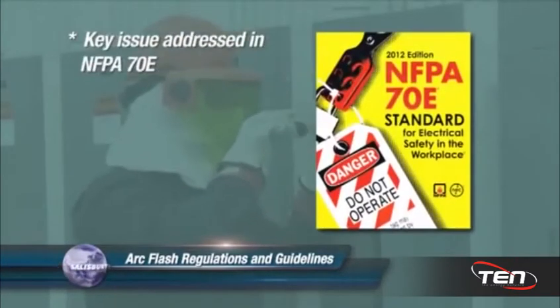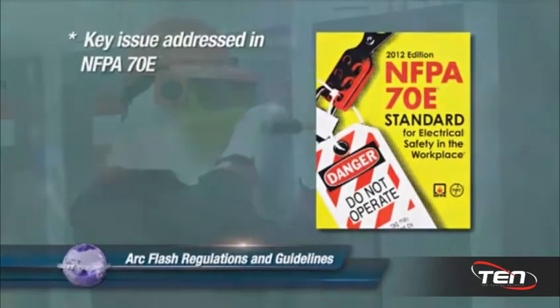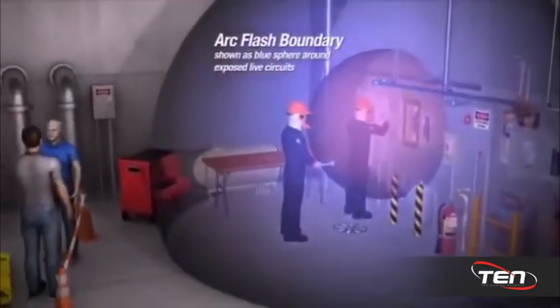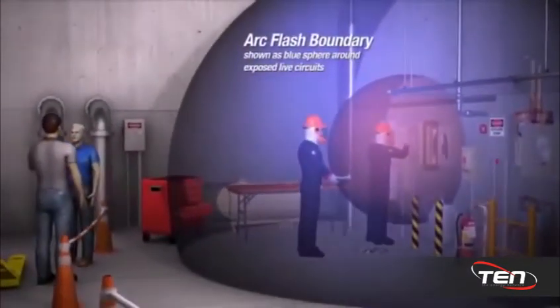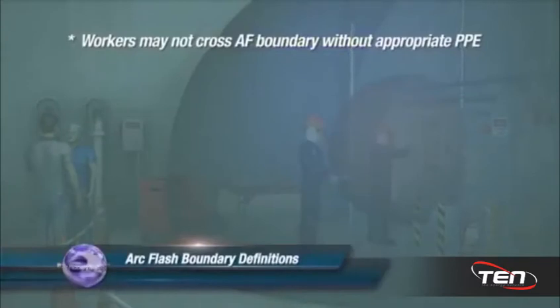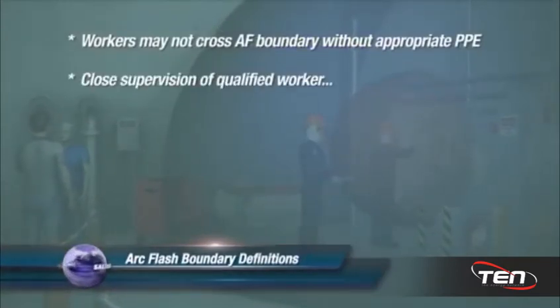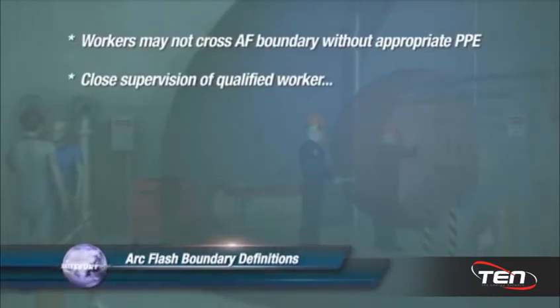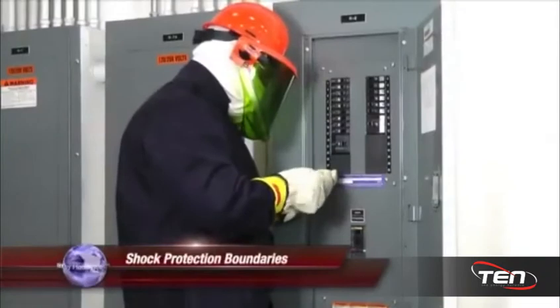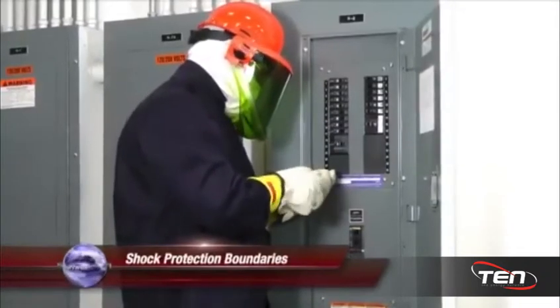The arc flash boundary is one of the key issues addressed by the NFPA 70E standard. The arc flash boundary is the approach limit at a specific distance from exposed live parts within which a person could receive a second-degree burn. Workers may not cross this boundary without the appropriate personal protective clothing and the close supervision of a qualified worker who has the necessary certifications and has been properly trained. In addition to the arc flash boundary, there are shock protection boundaries.